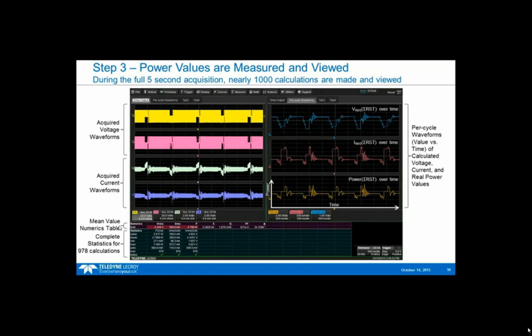Here's the mean value of the table, where we're calculating the mean values. The voltage is changing quite a bit, and this is the plot of the voltage over time. A mean value doesn't tell me much. Even a statistics set of about 1,000 calculations tells me a range, the mean, the worst case, and the standard deviation, but nothing beats being able to just see that value plotted over time. So I've got a lot of data here to look at. If all I had was a mean value in this waveform, I wouldn't have picked up that I might have some problem here with one of the directions of the motor travel.